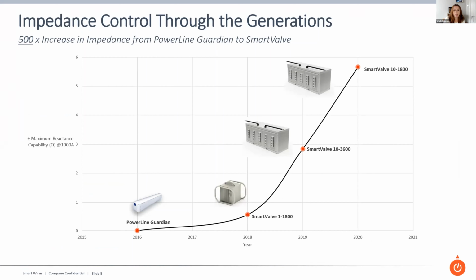So we are now with the Smart Valve 10-1800, which has its first deployment next year, injecting about 500 times more impedance from that device than we were from a Powerline Guardian 5 years ago. So that's a really dramatic increase in capability. We are operating up to 3,600 amps continuous in some installations, 1,800 amps in other installations, and we have a fault current capability of 63,000 amps, but also the capability to increase that to 80,000 amps where it is needed.